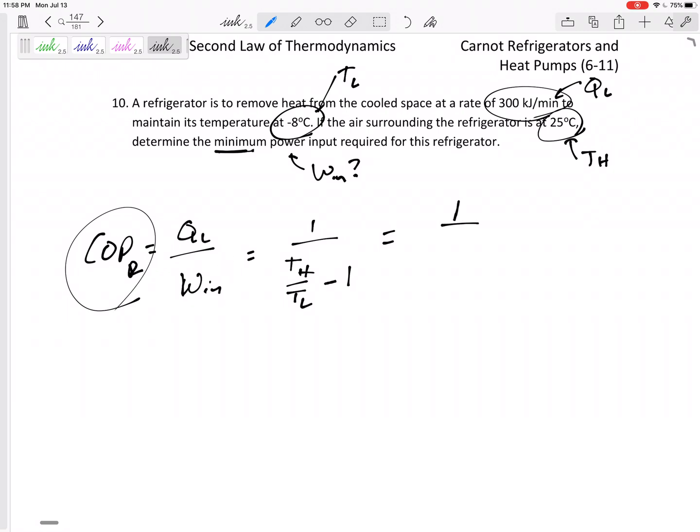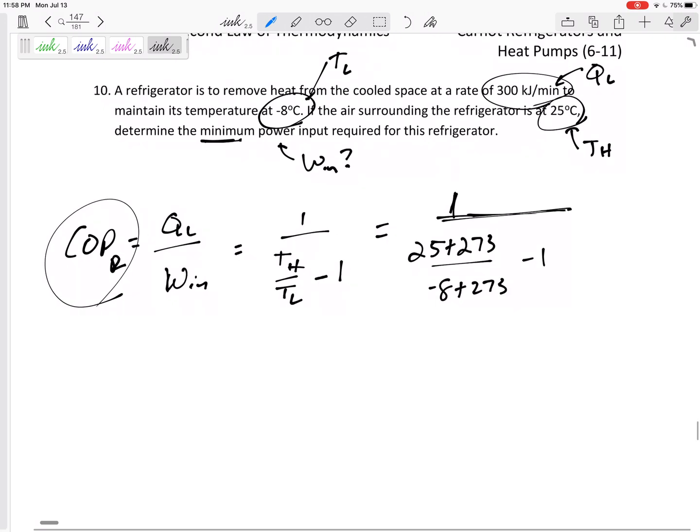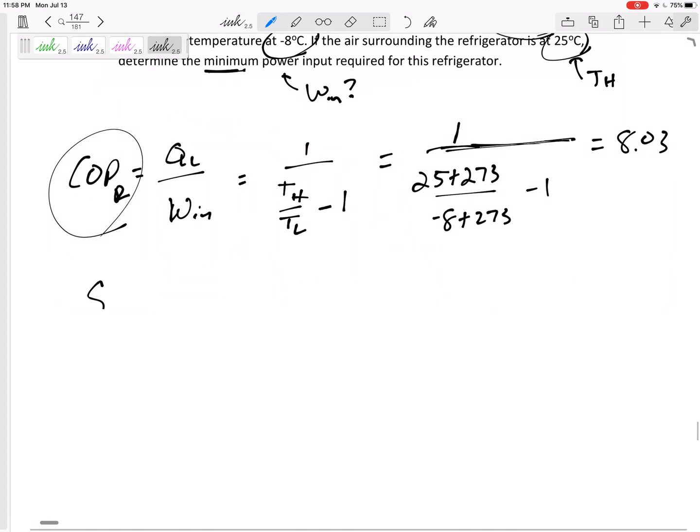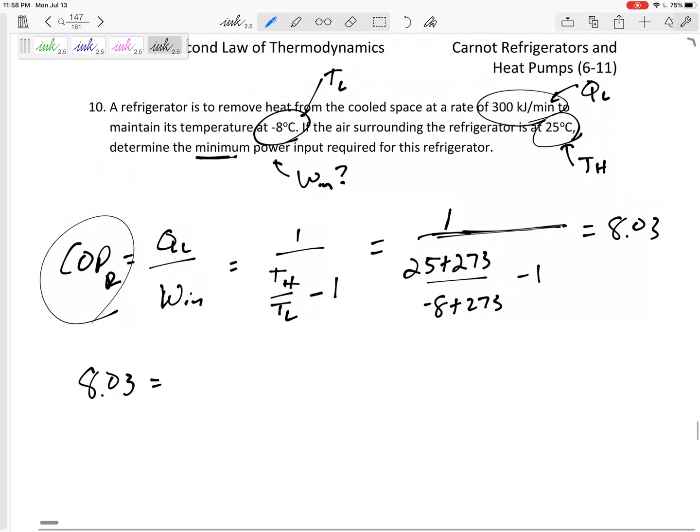So this would be one over TH, 25 plus 273, over negative 8 plus 273, minus one. Be careful with the math, don't make silly math mistakes. Coefficient of performance: 8.03.